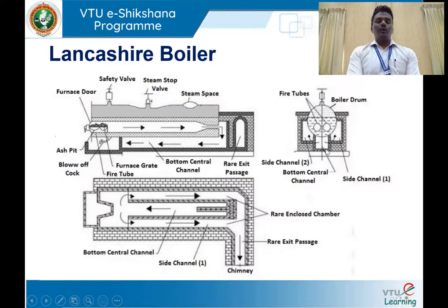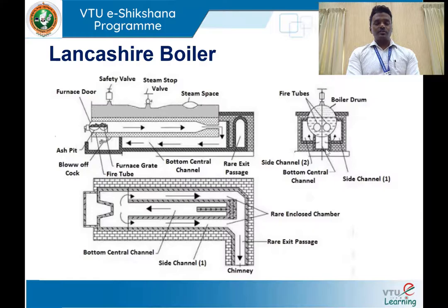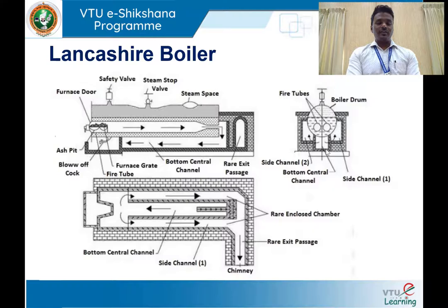Coming to the working principle of the Lancashire boiler — using this boiler, we can generate steam at low pressure, up to 20 bar. When fuel is burned inside the furnace — coal is used as fuel in the Lancashire boiler — it releases hot gases. Those hot gases are made to flow through the flue tubes. In order to prevent entry of dust particles or combustion particles inside the flue tubes, there is a bridge provided at one end of the flue tube.